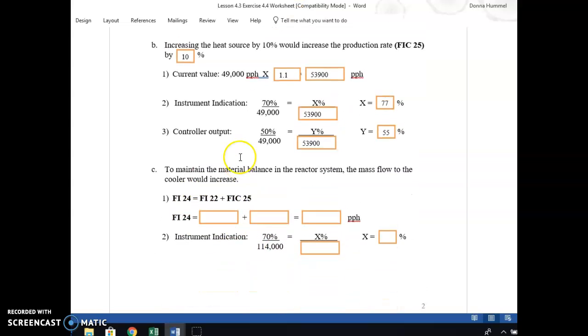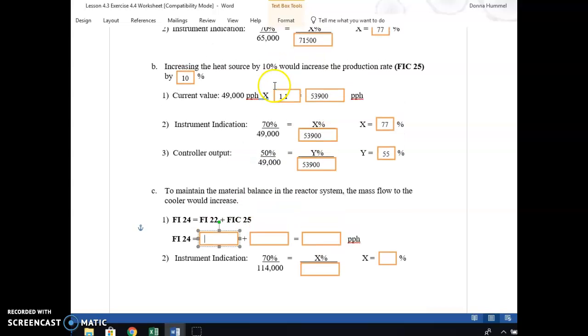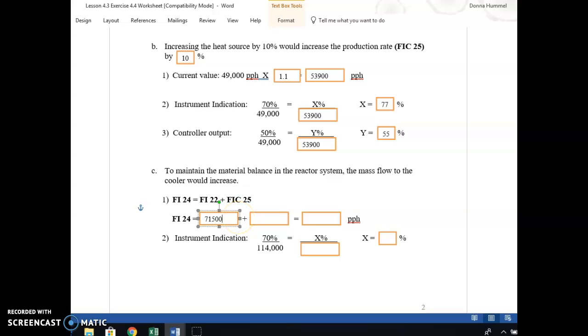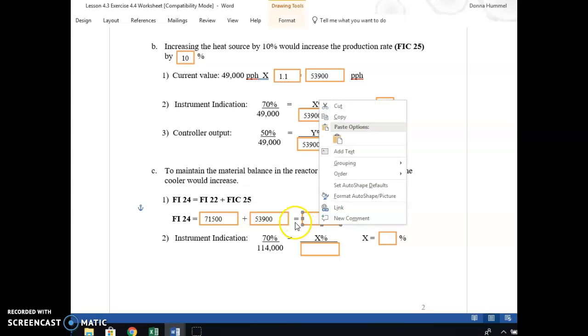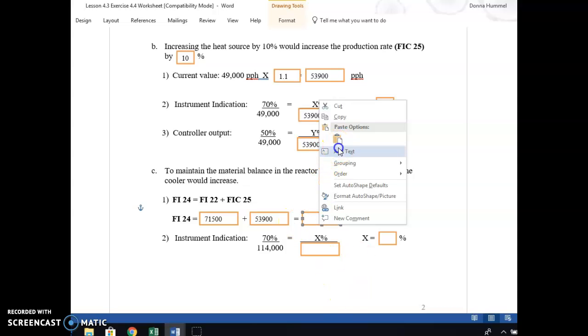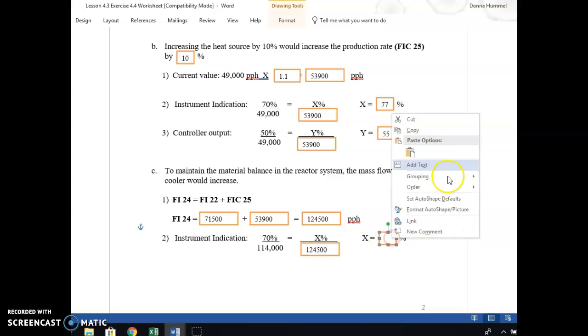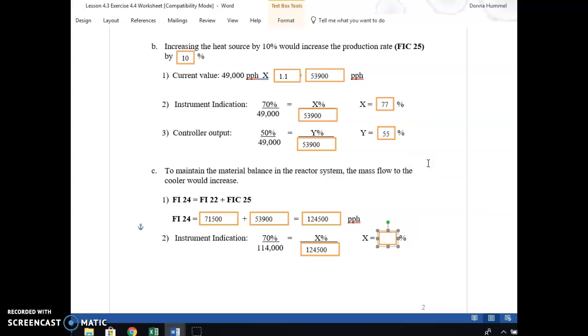Now, we're just going to total. We can do 10% of the output of what the pounds should be normally, which is 10% of this 114,000, but we could just add them all together. We know balance-wise that 71,500 plus 53,900 should equal the new number, and that is 125,400. If you take 1.1 times this 114,000, you'll get the same number. So what is the instrument indicating? Our instrument is at 70% for this normal flow of 114,000. So now we're going to take the ratio at 125,400. So now our number reading out of that instrumentation is 77%.